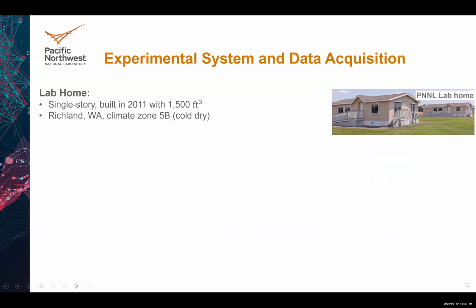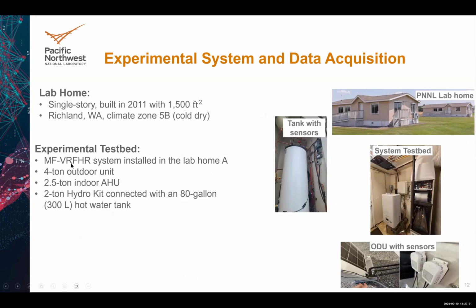From this figure, you can see we have two identical PNNL Lab homes. This is a single-family residential home in Richland, Washington State. We also have the MF-VRFHR system installed in one of the Lab homes. This system has a 4-ton outdoor unit, like in this picture. We have 2.5 tons for the indoor AHU. We also have 2 tons for the Hydro Kit. You see here, this Hydro Kit is connected with the hot water tank. The tank has 80 gallons, or 300 liters.